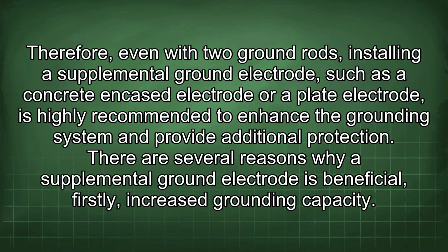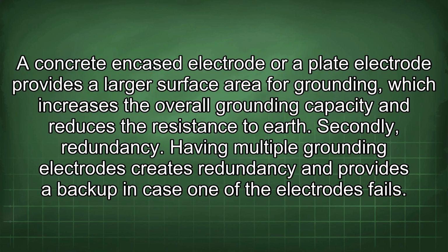Therefore, even with two ground rods, installing a supplemental ground electrode, such as a concrete encased electrode or a plate electrode, is highly recommended to enhance the grounding system and provide additional protection. There are several reasons why a supplemental ground electrode is beneficial. Firstly, increased grounding capacity. A concrete encased electrode or a plate electrode provides a larger surface area for grounding, which increases the overall grounding capacity and reduces the resistance to earth.